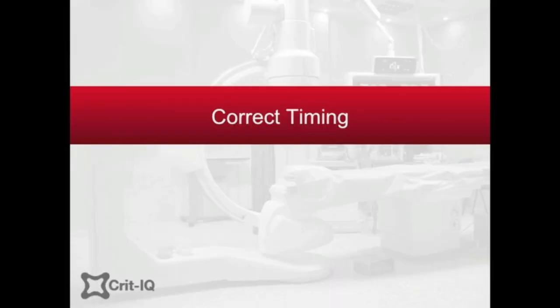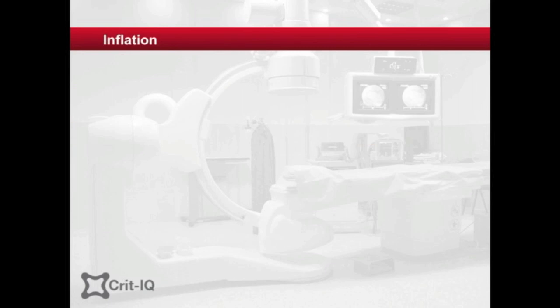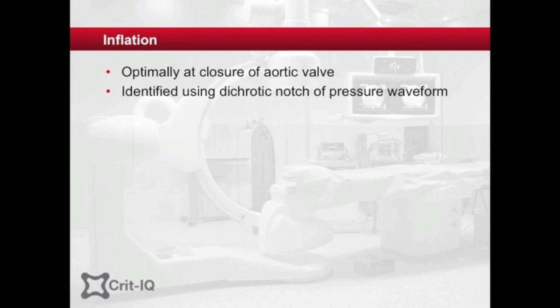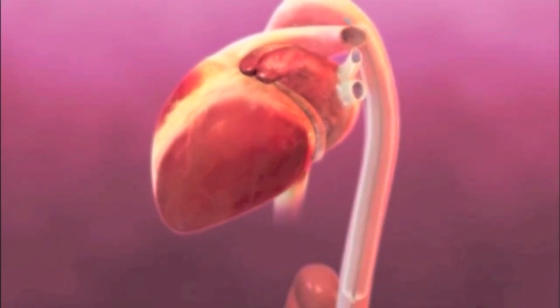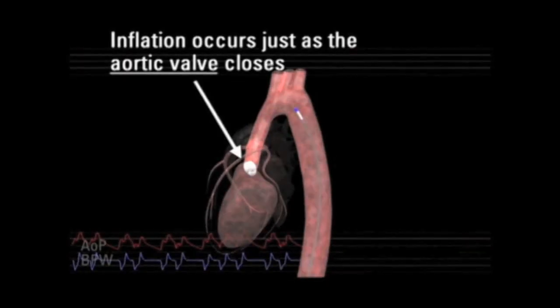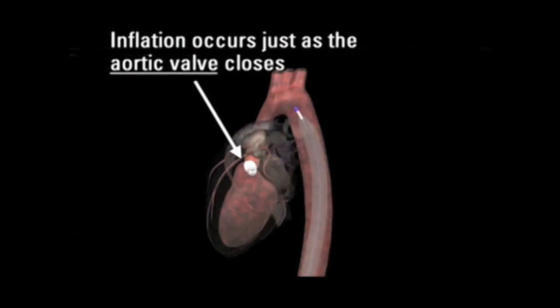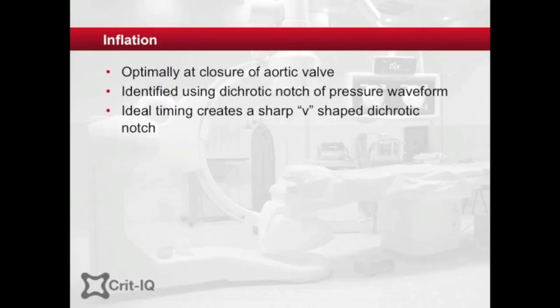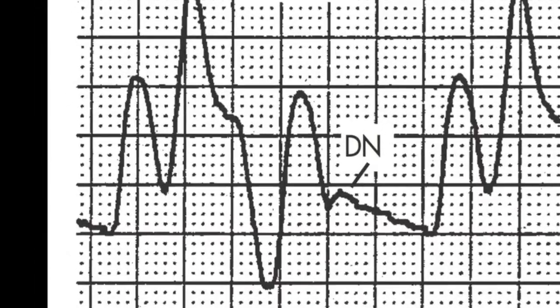The correct timing for inflation and deflation of the balloon is imperative to the functioning of the balloon pump. Inflation should be on closure of the aortic valve, marked by the dicrotic notch on the waveform. When the balloon inflates with the onset of diastole, blood is propelled under pressure through the coronary ostia above the aortic valve and into the coronary arteries, thus providing better perfusion pressures compared with the passive filling that occurs during diastole in the unassisted heart. With correct timing, the dicrotic notch should have a sharp V-shape.